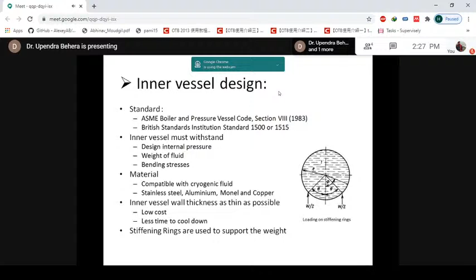This is the equation generally used, as per the ASME code: T, the thickness of the cylindrical shell, equals P into D by 2 SA EW minus 1.2P. Here P is the design internal pressure, D is the inner diameter of the shell, SA is the allowable stress, and EW is the welding efficiency.